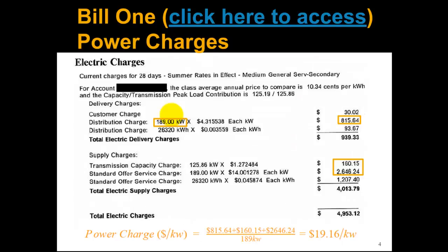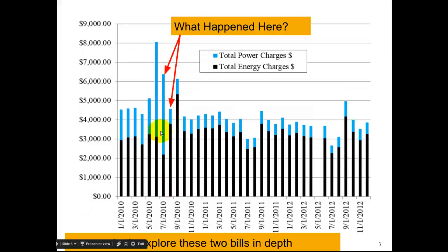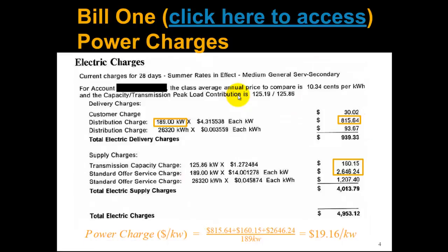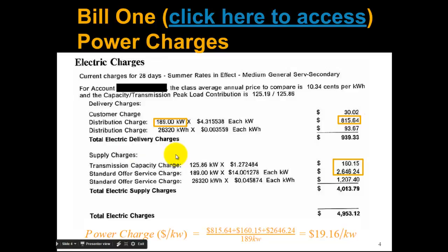Let's look at what happened here first. If we look at the first bill — the bill with the high power charges — they were being charged for delivery and supply from the power company themselves; there wasn't a third party supplier. If we add up all the different power charges and divide by the 189 kilowatts, we get more than $19 per kilowatt, which is actually pretty expensive. The big portion of that is really this $14 in the supply charges.